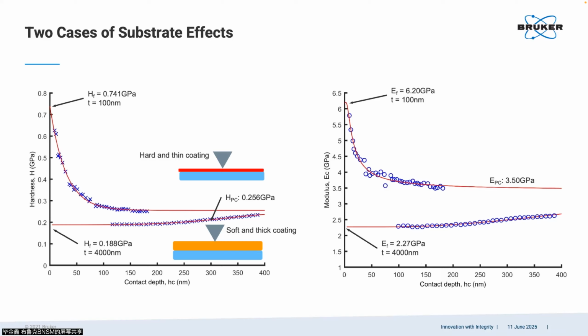I have these two typical cases for you. You can see that for these two cases, the substrate is exactly the same. We have a very thin and very hard top layer, so we have the hardness trend with depth like this. You can see the hardness decreases very dramatically when the contact depth is going up. And this is the modulus, similar behavior. Another case is a thick and softer top layer on exactly the same substrate. So the behavior is here. It's totally opposite behavior, and the tendency is not so fast because your film thickness is higher. So this is the idea.